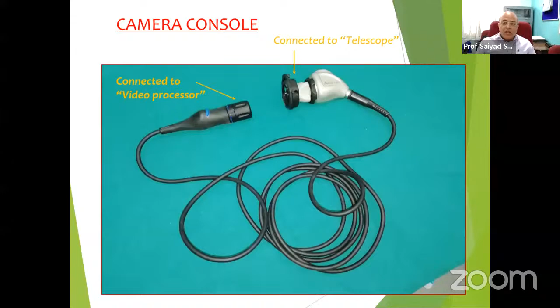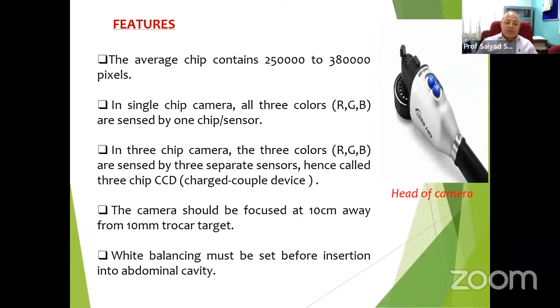In a single chip camera, all 3 colors are sensed by the 1 chip or 1 sensor. That means the quality will not be good. In a 3-chip camera, the 3 colors, red, green, and blue, are sensed by 3 separate sensors, hence called 3-chip, that is charge coupling devices. The camera should be focused at 10 centimeters away from the 10 millimeter trocar target. White balancing must be set before insertion into the abdominal cavity.